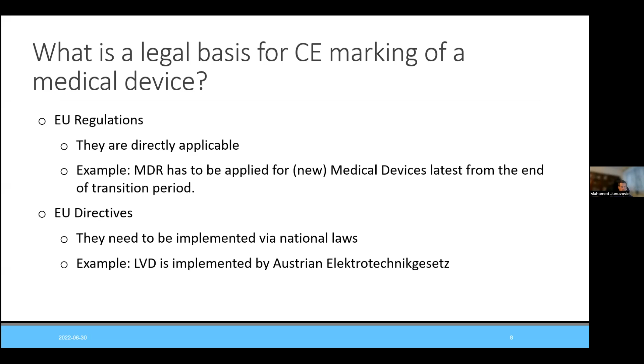Regarding, let's say, law for the medical industry, there are two main types: regulations and directives. Regulations are applicable immediately. So as soon as a new regulation is announced, each manufacturer needs to apply it on an existing or a new medical device. Directives are a little bit different. They are usually implemented via national laws. For example, there is the Low Voltage Directive, which in Austria is implemented by the Austrian Elektrotechnik Gesetz. It is on the manufacturer to find out which regulations or directives are applicable for a particular device.